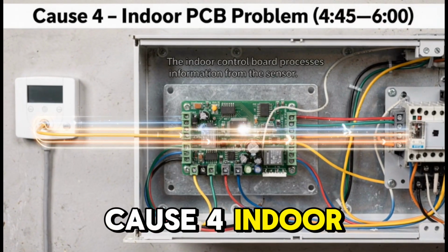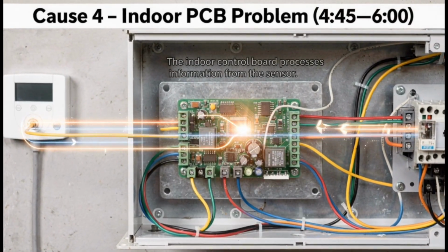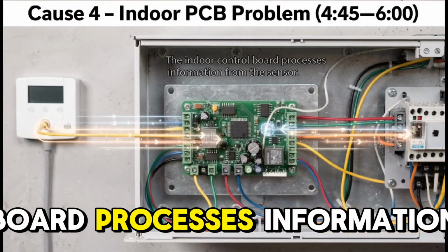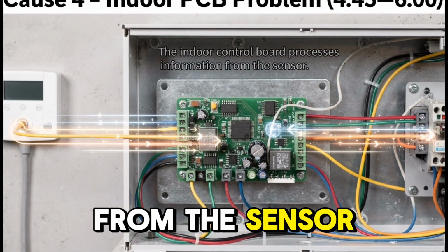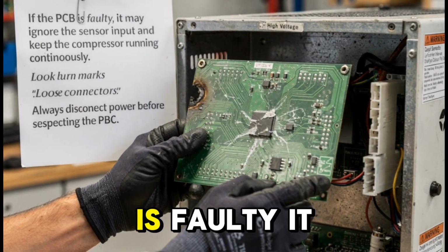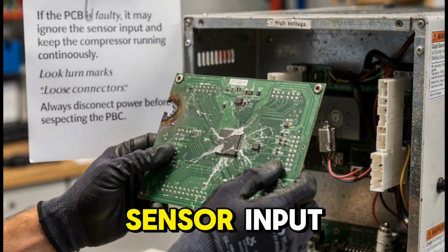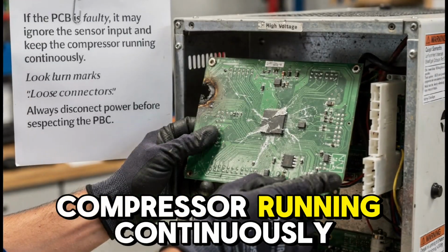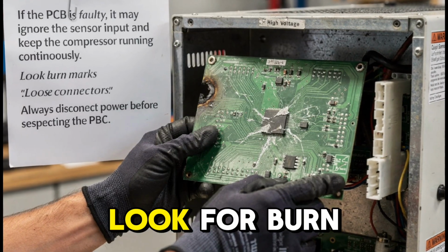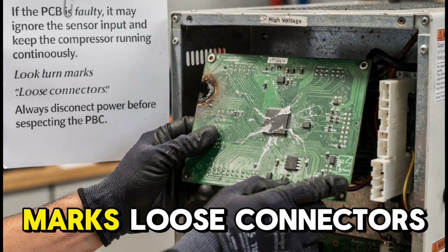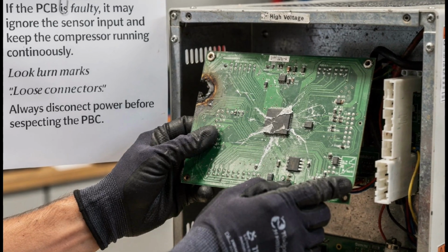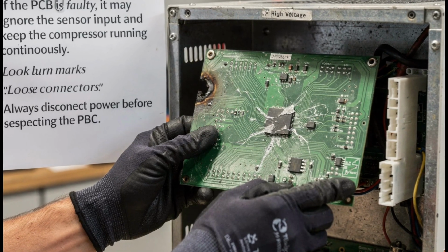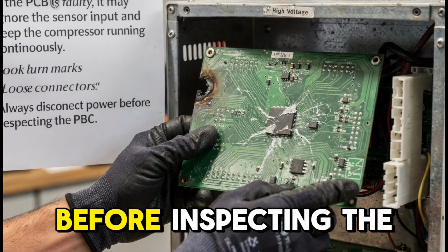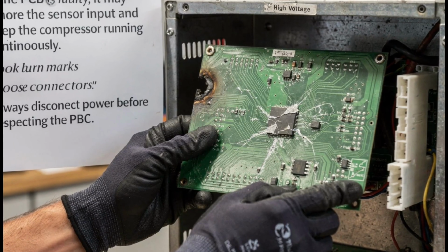Cause 4. Indoor PCB problem. The indoor control board processes information from the sensor. If the PCB is faulty, it may ignore the sensor input and keep the compressor running continuously. Look for burn marks, loose connectors, damaged components. Always disconnect power before inspecting the PCB.